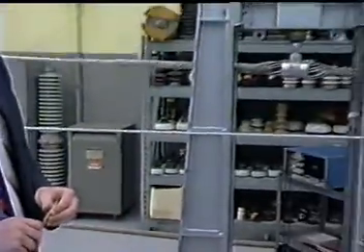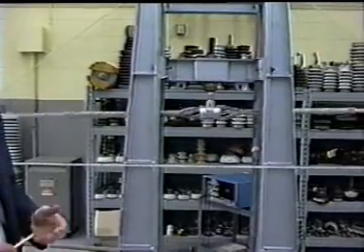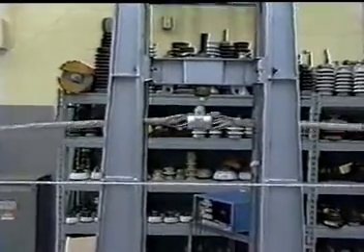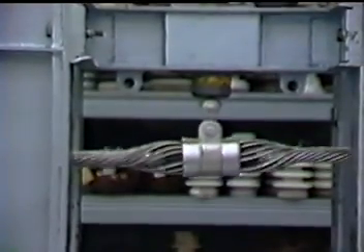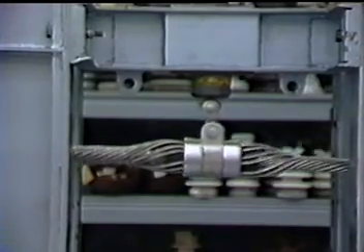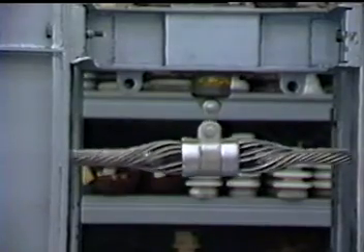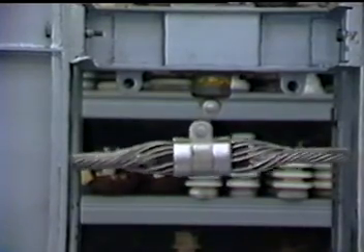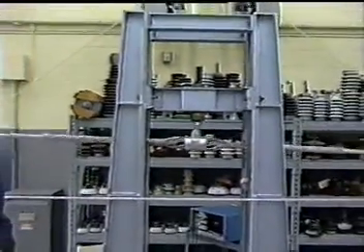In the real world, galloping is much more destructive, and that's because the spans are much longer, and therefore the conductor has a lot more mass to it. So there are limitations to how much damage we can simulate in the laboratory in comparison to the real world damage that's being done in the field. In the real world, where you have a 300-meter span, you can imagine the amount of mass of the cable as it oscillates up and down causes much more damage to the hardware at the location.